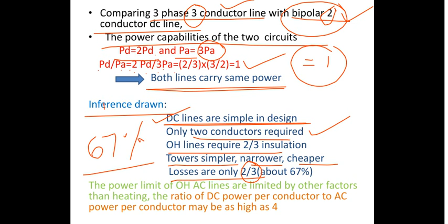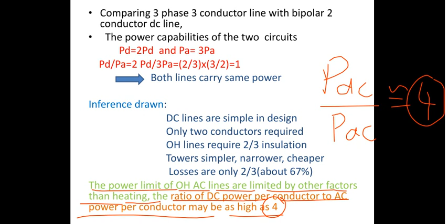That means only about 67% of the total losses are incurred in the case of HVDC system compared to a similarly rated HVAC system, right? And there are certain other factors also which you need to consider. The power limit of the overhead AC lines is limited by factors other than heating, right? We have already seen some of the points: skin effect, it may be corona effect, or there may be some other parameters as well, right? So therefore, by considering all these things, we can have the ratio of DC power per conductor to AC power per conductor to be as high as almost equal to 4, right? So this is one important conclusion which you can draw when you compare the AC power as well as the DC power per conductor and per circuit.